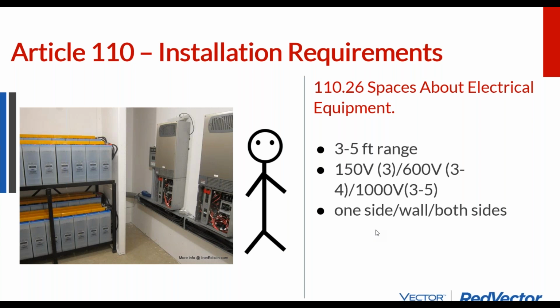Is there electrical equipment behind you? Or is there a wall behind you? Or is there nothing behind you? It's like, well, that's weird. Why do I need to have dedicated space if there's nothing behind me? You can't put storage in that space. So if there's nothing behind you, you're dealing with a 3-foot requirement. But if there's something behind you, if there's a wall behind you, you need some additional footage. And then if there's electrical equipment behind you, you need even additional footage than that. And if there's high voltage electrical equipment behind you, you need even additional footage than that. And that range is between 3 feet and 5 feet.